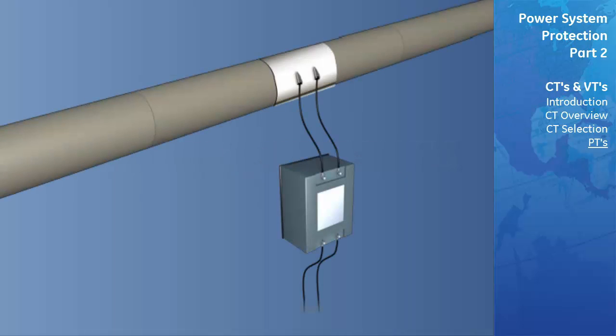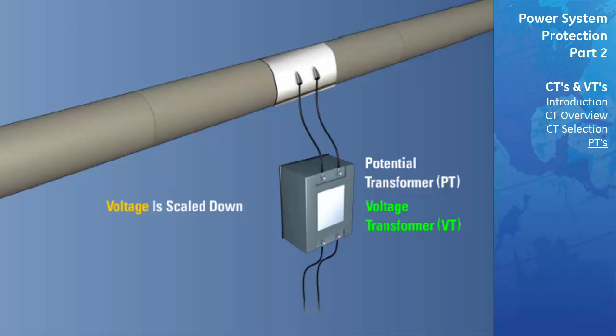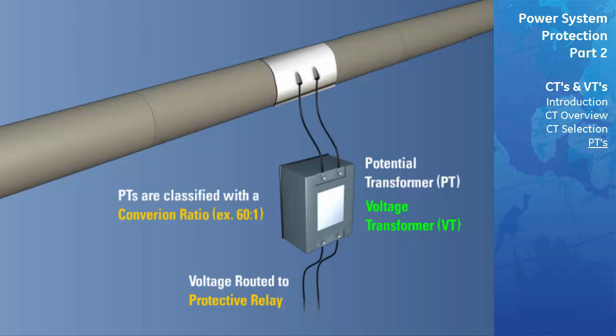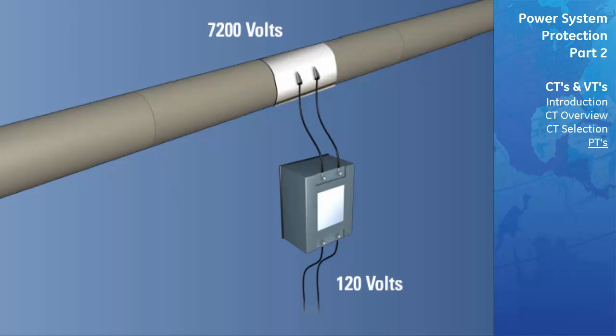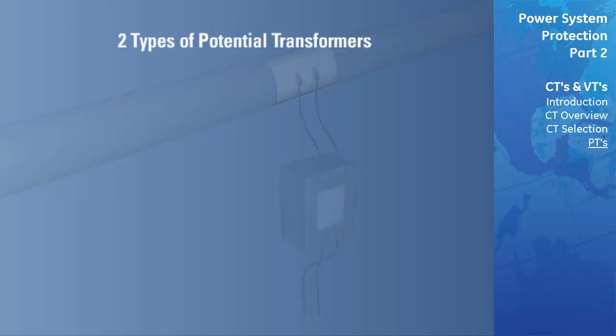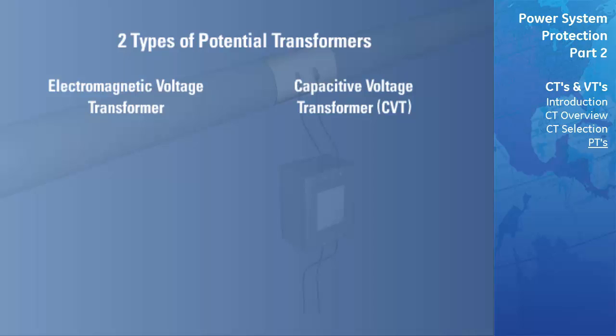The next type of transformer we will cover is the potential transformer, symbolized as PT, or sometimes known as a voltage transformer, symbolized as VT. Similar to current transformers, potential transformers scale down the voltage passed through them. The scaled down voltage is then routed to a protective relay for measurement. A PT is classified with a conversion ratio indicating the amount the primary voltage is scaled down — for example, 60 to 1 scales the primary voltage down to 120 volts. There are two different types of potential transformers used today: the electromagnetic voltage transformer and the capacitive voltage transformer.